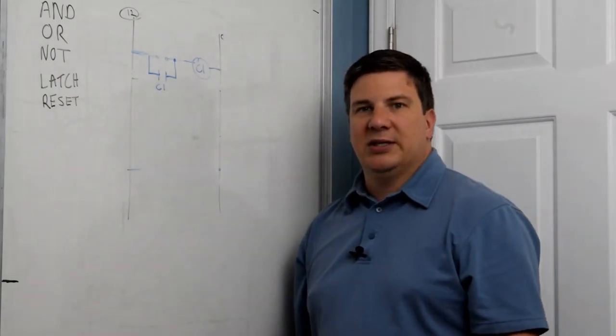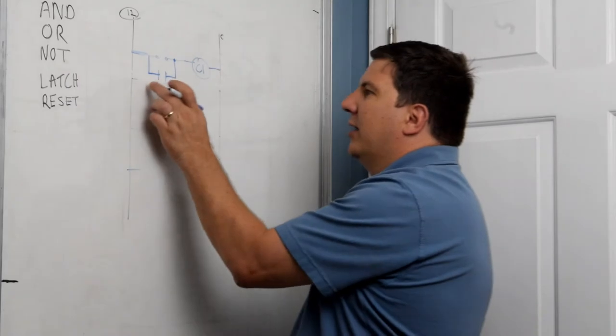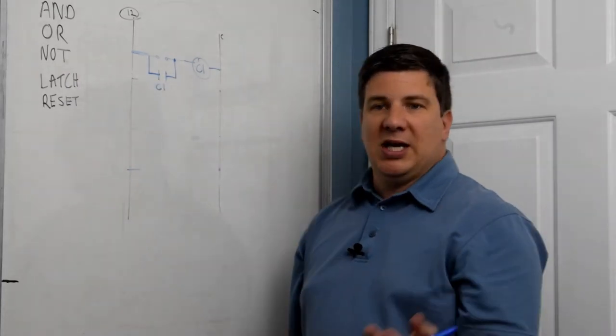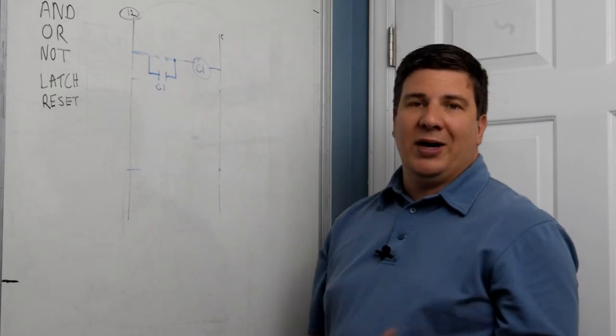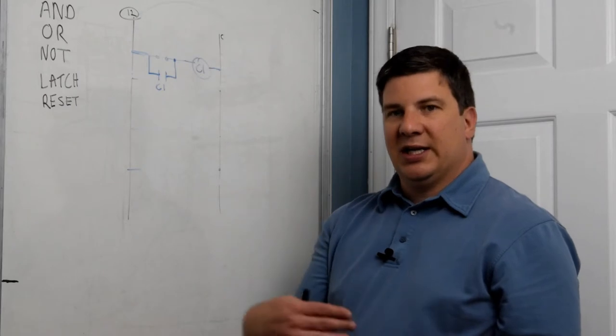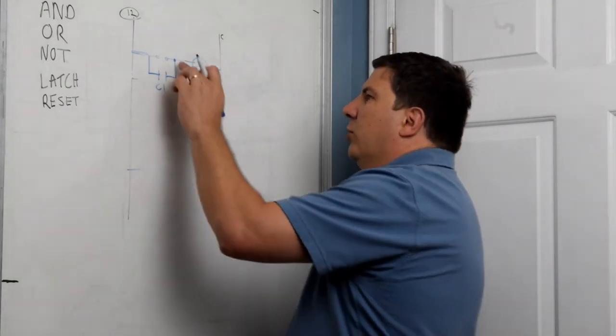But what if I want to stop it? So I've got my latch function here, but I have no way to stop it. Well, my e-stop is a button and I'm going to wire it so that as long as I'm not pushing it or if it's a latching type, that it's out, it's going to be a normally closed.